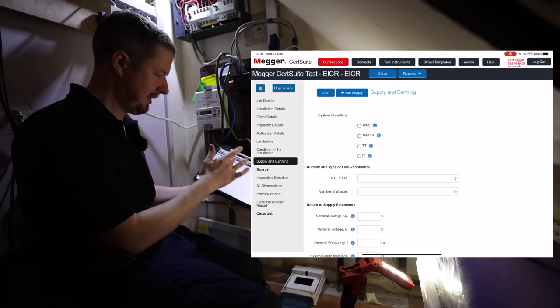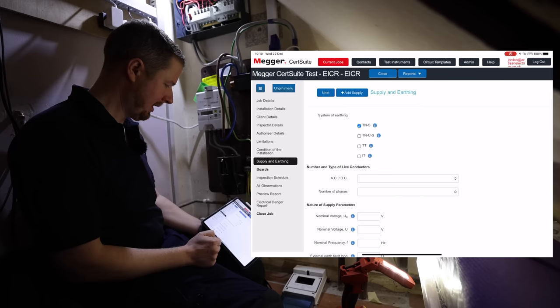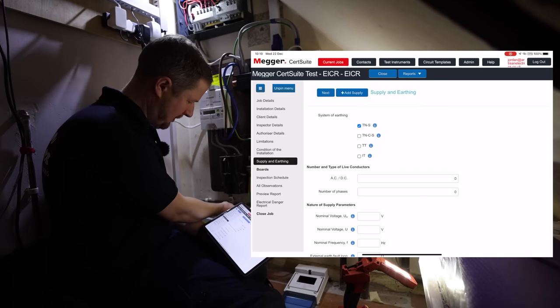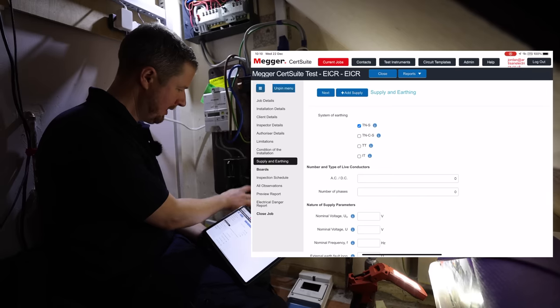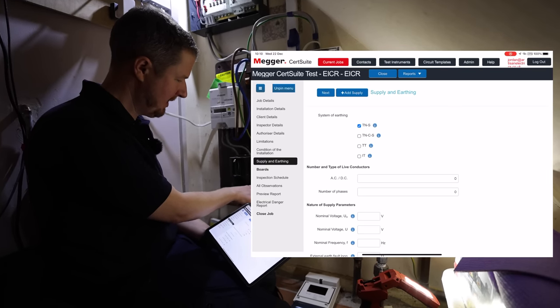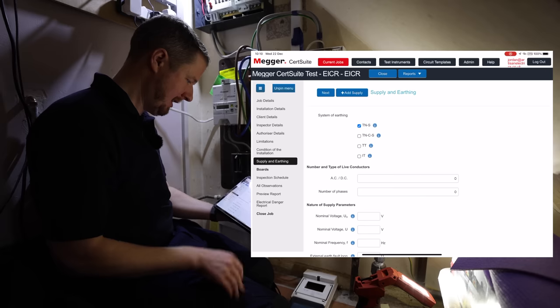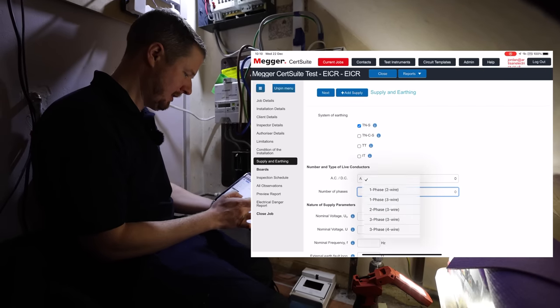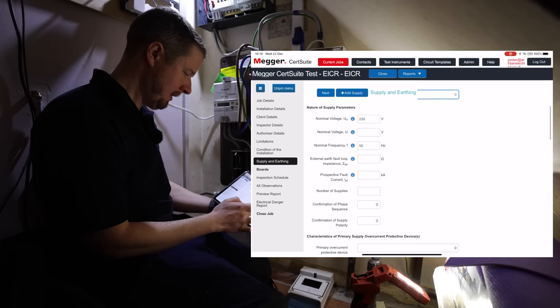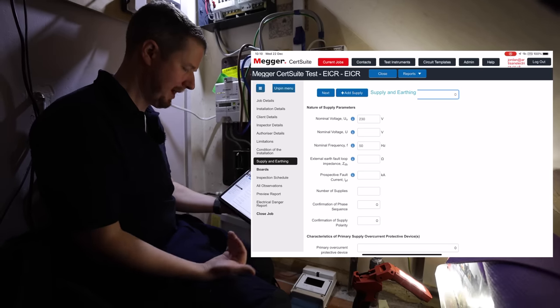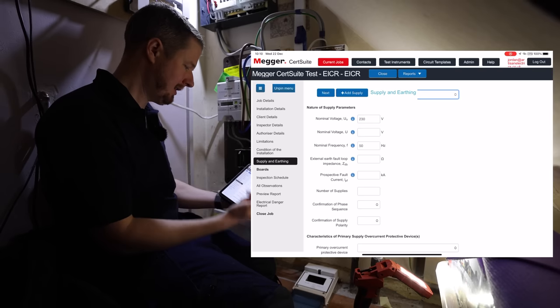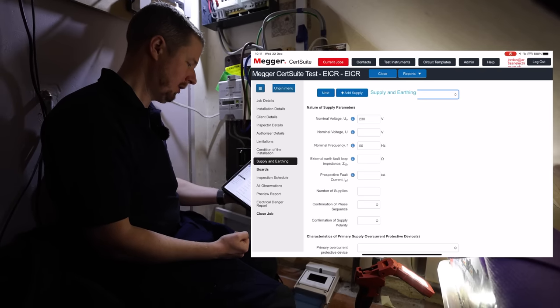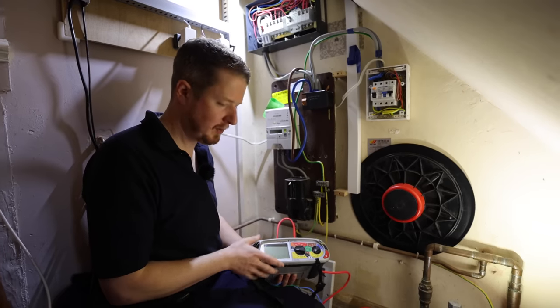Supply and earthing, that's where we're going to start now. So it's a TN-S system, so we click the TN-S box. That is because the earth comes off the sheath of the supplier's cable, and Lee has nicely labeled these up so that's fine. That is 16mm. It's an AC system, one phase, two wire, nominal voltage 230 volts, frequency 50 hertz. It automatically fills this out for us.